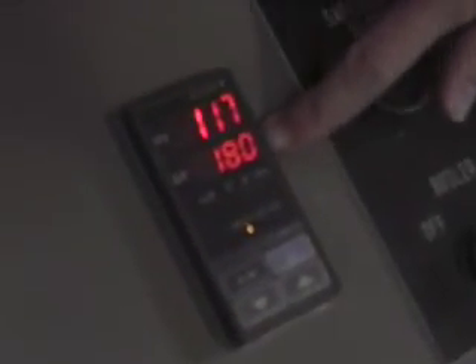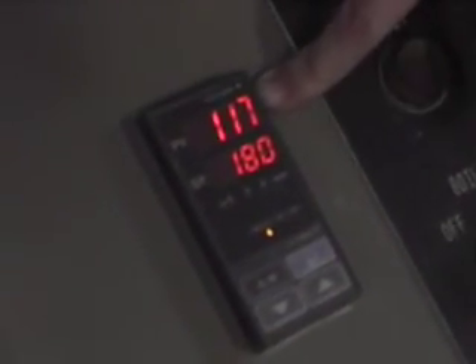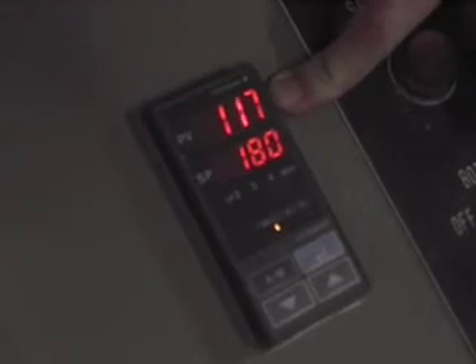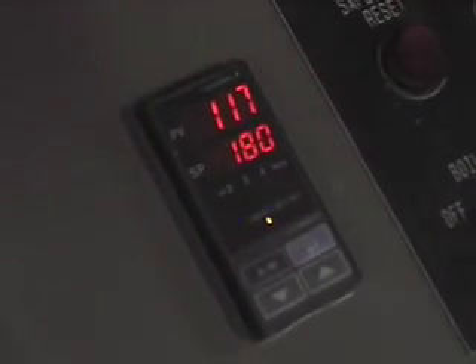All right. So that's where the adjustments would be made. This is where you're going to be looking to make sure that everything's good, and that's the daily. I'm sorry. That's the weekly. The daily, you're just observing the temperatures. Now this is kind of an interesting setup. You see that my set point is 180, and that we're measuring, this is on the discharge side of the boiler, 117 degrees, and I've got a heat demand. Well, this is being bypassed, so don't pay any attention to the temperature that's being read here, it's the set point. Okay?